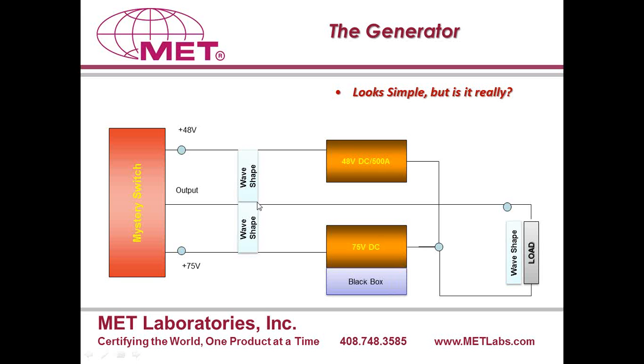In addition to these challenges, the other challenge is wave shaping. Close to the red box, which is marked as switch, I have labeled 2 wave shaping circuits. These circuits are a combination of resistor and capacitor. They not only help us get rid of the overshoots, they also help us achieve the correct rise time and fall time. In addition to that, for the overvoltage waveform where the rise has to be 10 volts per millisecond, we have another combination of a diode and a resistor-capacitor combination. Please keep in mind that the resistor-capacitor combination close to the load, which hooks up in parallel to the load, will have to be tunable, in other words selectable with a switch, basically a bank of resistors and capacitors selectable with mechanical switches.